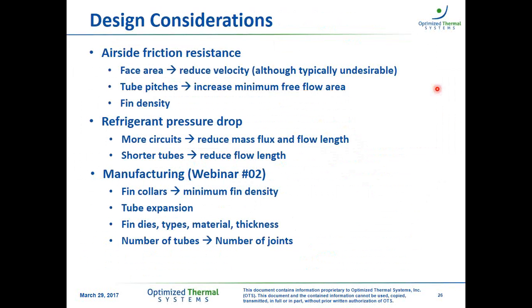Now, on webinar number 2, which I highly encourage you all to register and attend, there are some manufacturing aspects that also need to be considered in terms of heat exchanger design, and they will actually go hand in hand with some of the design challenges from a performance perspective. Just an example here, fin collars. The collars are basically the extra material from the fin that separates one fin from the other. If we have a very small diameter tube, the actual fin collar is not long enough to actually get a good distance between the fins. So there's a minimum fin density that you need to have, and that might be an additional constraint when you're thinking about reducing pressure drop.